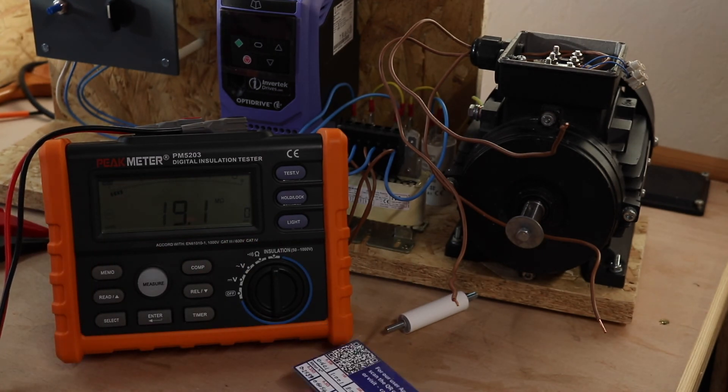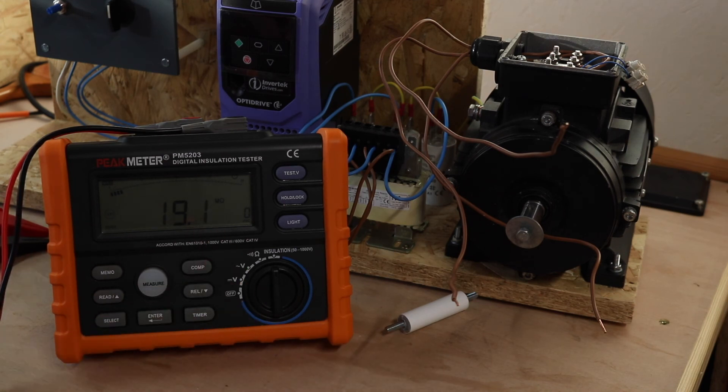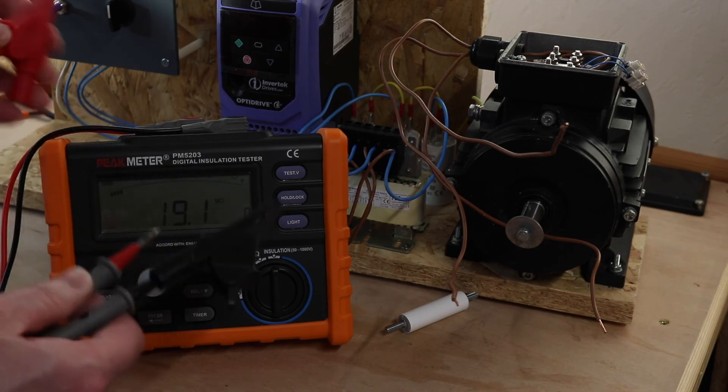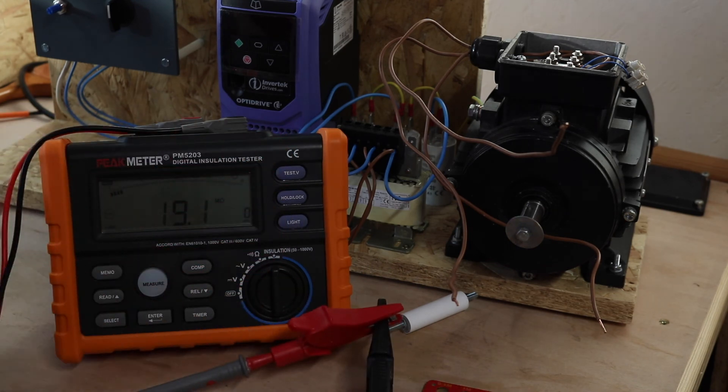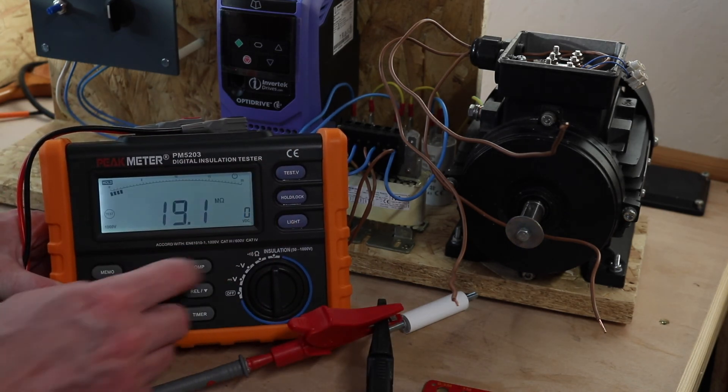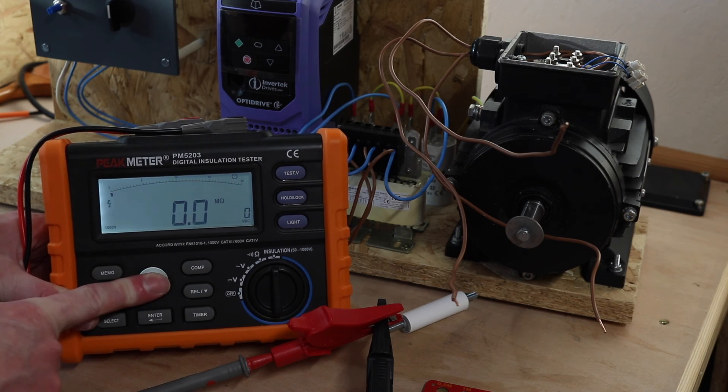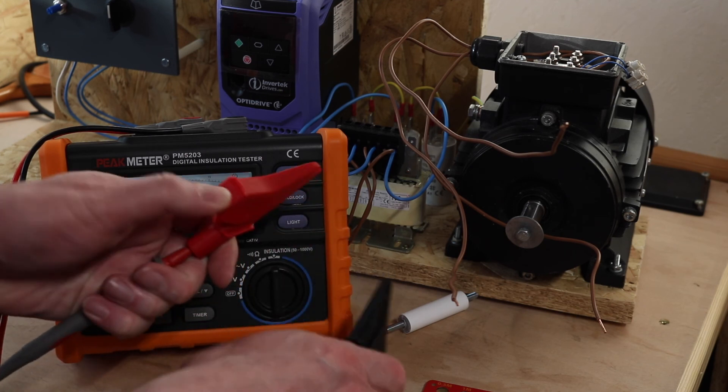And finally, the other check you can do with your insulation test to see if it's working okay is basically just short your leads out and you should get a zero reading on your instrument. And then you see zero there.